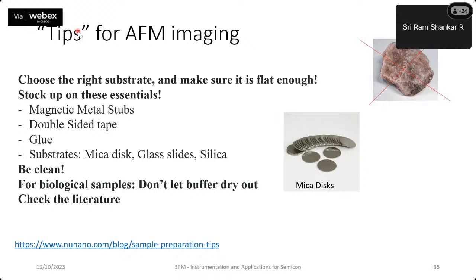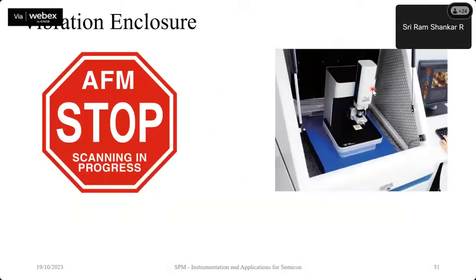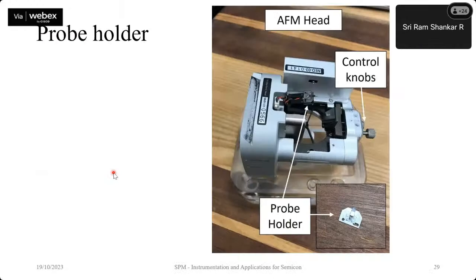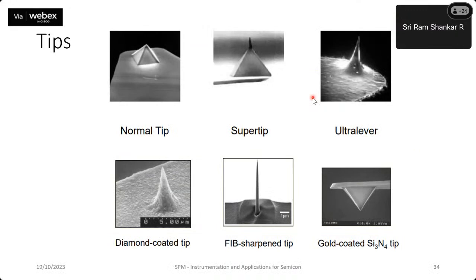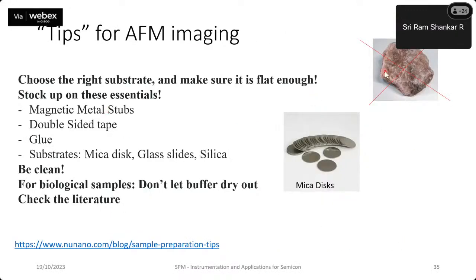Use the right substrate and make sure it is sufficiently flat. If you use a rough kind of substrate, there's a possibility that the tip isn't the part making contact with the sample. To ensure that only the ultimate end of the tip contacts the sample, you need atomically flat samples, which requires quite some polishing and other preparation techniques, and the substrates need to be quite clean. Some examples are mica discs, glass slides, and silica discs, and so on.